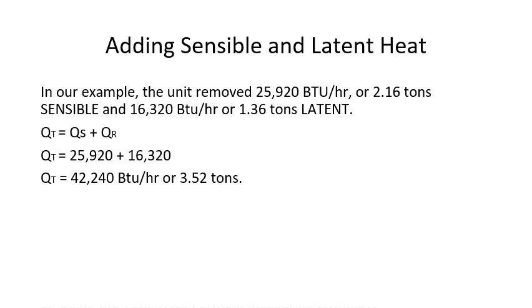Let's talk about adding sensible and latent heat together. In our example, the unit removed 25,920 BTUs per hour of sensible and 16,320 BTUs of latent heat. To calculate total heat, we just add those two numbers together — sensible plus latent — and we arrive at 42,240 BTUs per hour, or 3.52 tons.